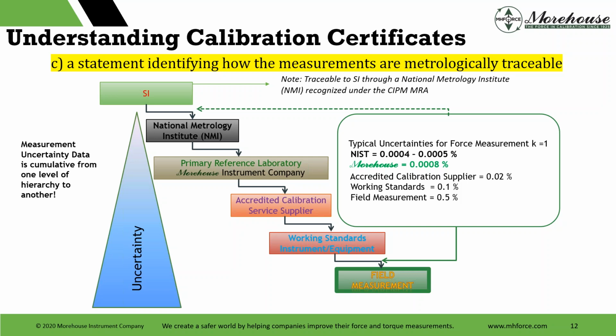Per the NIST website, metrological traceability requires the establishment of an unbroken chain of calibrations to a specified reference standard, typically national or international standards, in particular realization of the measurement units of the International System of Units, SI. NIST assures the traceability to SI. The next tier in the pyramid is a primary reference laboratory. This is like us, Morehouse Instrument Company. Our traceability to SI is validated by NIST calibrations on several deadweight force machines. Morehouse provides metrologically traceable force transducer calibrations to SI units by applying a relatively known force using deadweight primary standards.